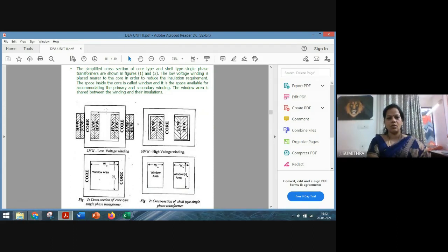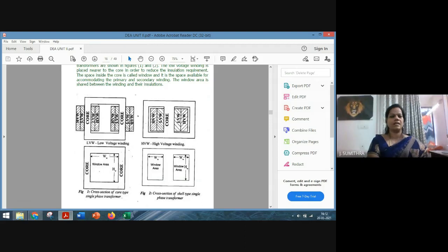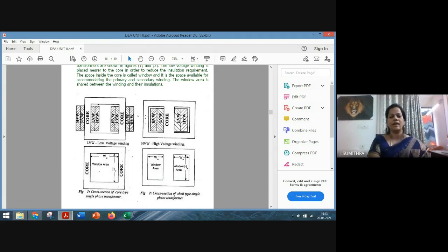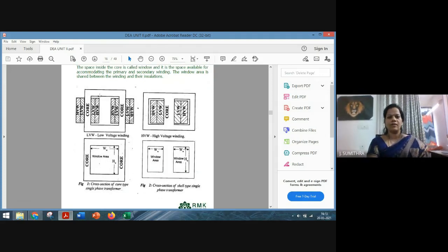A transformer has different parts: the core and the yoke. The top and bottom horizontal sections are known as the yoke, and the two vertical sections are known as the limb or the core. Next to the core, you always place the low voltage winding, followed by the high voltage winding. In a single limb, we place the low voltage winding next to the core followed by the high voltage winding — each and every limb in the transformer has windings. In a single phase transformer, we have a single window — the window is the area present between the two limbs.